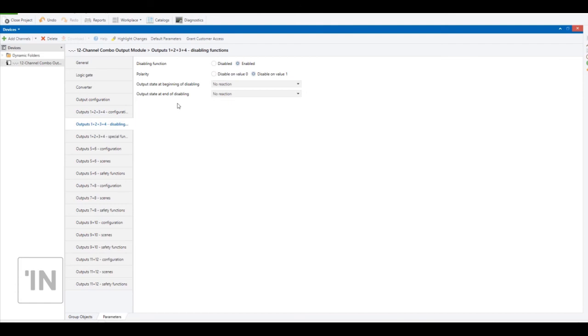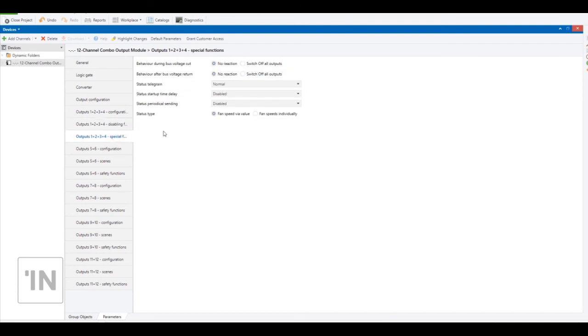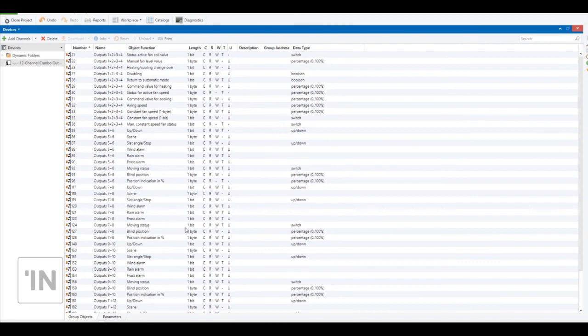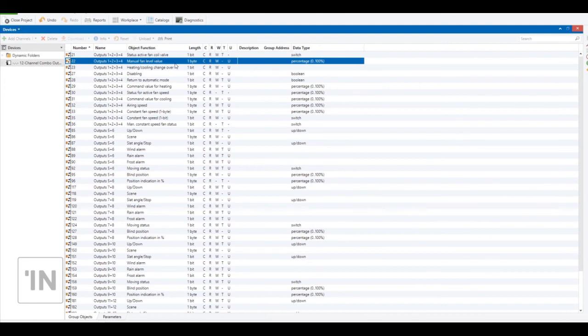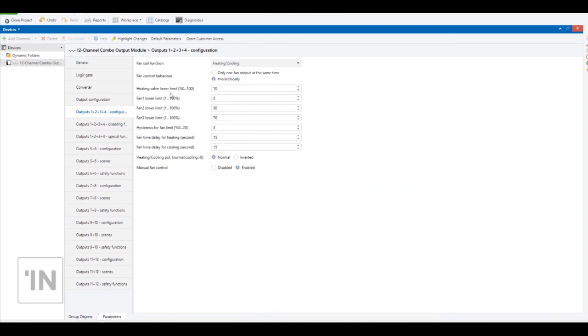Disabling functions and special functions — we have talked about similar parameters in previous videos so I won't repeat them. We can check the group objects. Manual fan level value is a one-byte object. When you send a percentage value, it opens the fan level according to your percentage value and checks the configuration. For example, when you send 25%, it opens fan level one; when you send 50%, it opens fan level two.